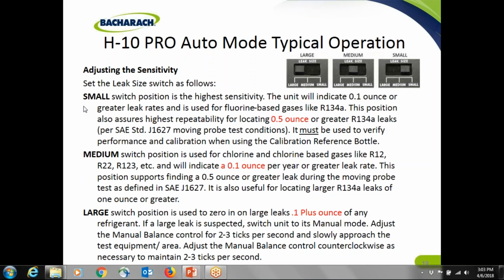Medium switch. The medium switch position is used for chlorine-based gases like R12, R22, R123, etc., and will indicate a 0.1 ounce per year or greater leak rate. This position supports finding a 0.5 ounce or greater leak during the moving probe test as defined in SAE J1627. It is also useful for locating larger 134A leaks of 1 ounce or greater. The large switch position is used to zero in on large leaks, 0.1 plus ounce of any refrigerant.